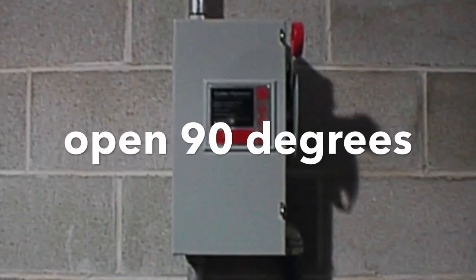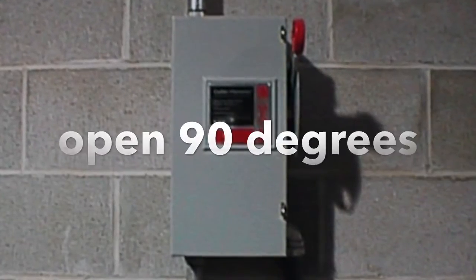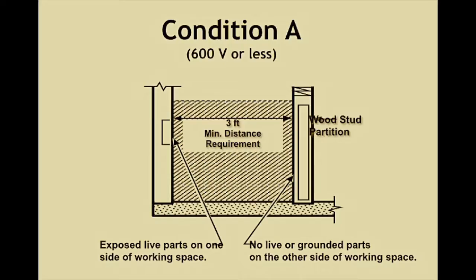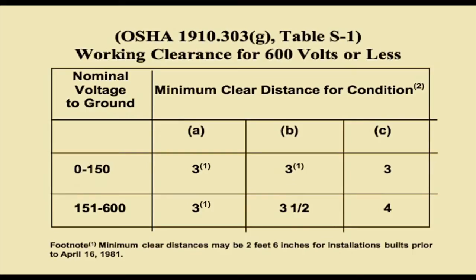Equipment doors and hinge panels must open at least 90 degrees. Here we see a diagram with the minimum distance requirement of 3 feet with exposed live parts on one side of the working space at 600 volts or less. Here we see the working clearance for 600 volts or less, according to OSHA 1910.303(g), Table S-1. We have our nominal voltage to ground and minimum clear distance for condition.